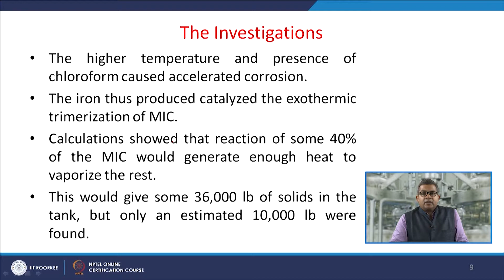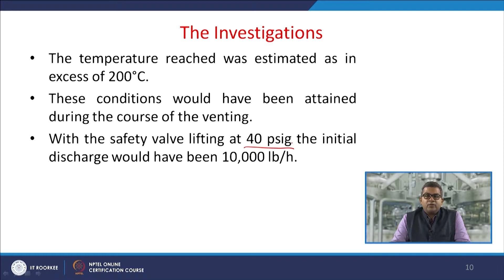Now these conditions would have been attained during the course of venting. The safety valve was designed to lift at 40 psig, and the initial discharge would have been 10,000 pounds per hour. So the report put forward the hypothesis that water was directly introduced into tank number 610, either deliberately or by mistake, through the process vent line, nitrogen line or other piping.